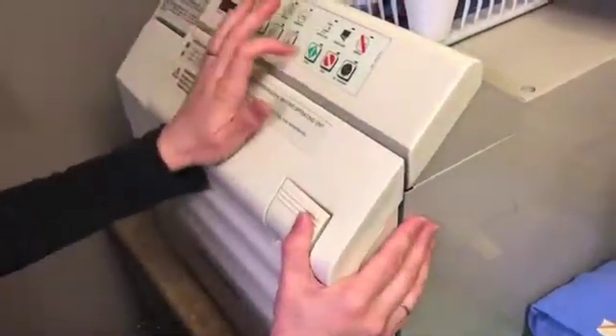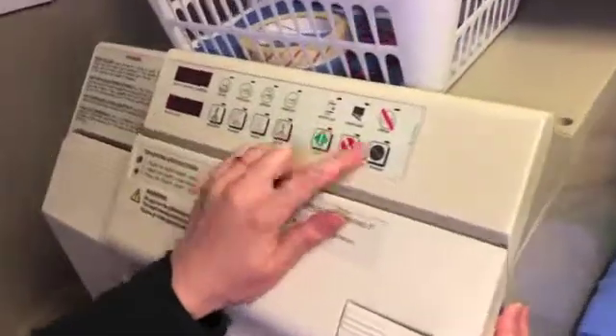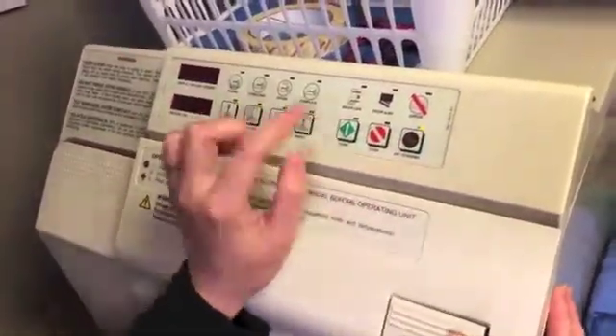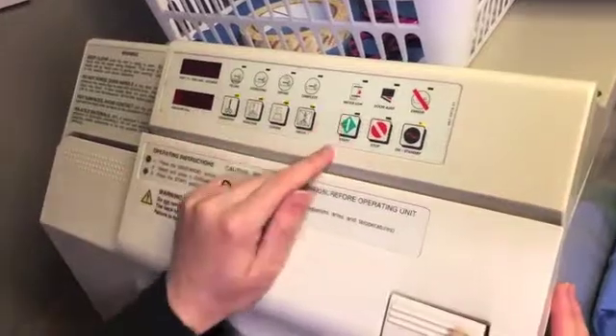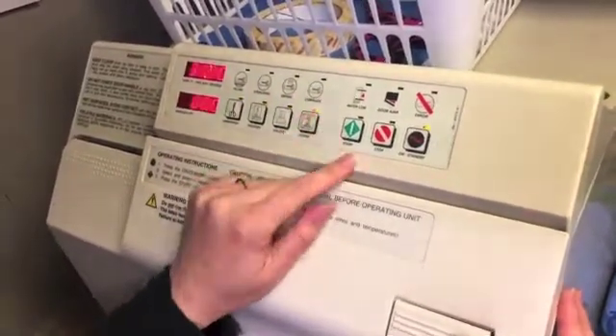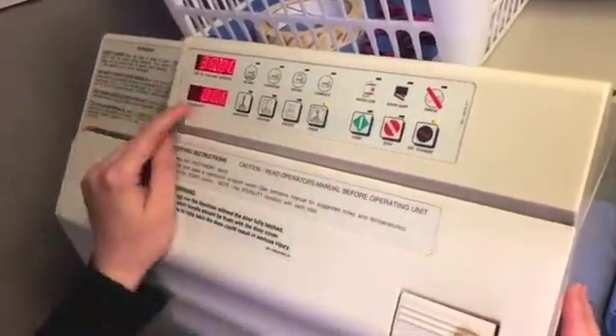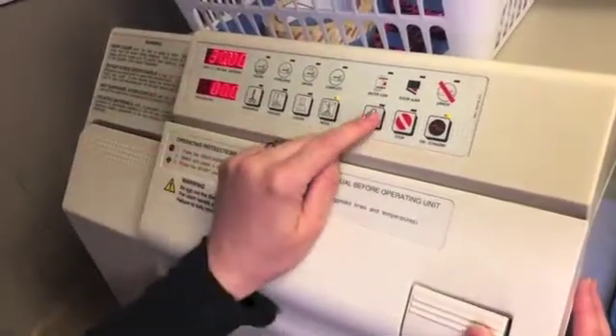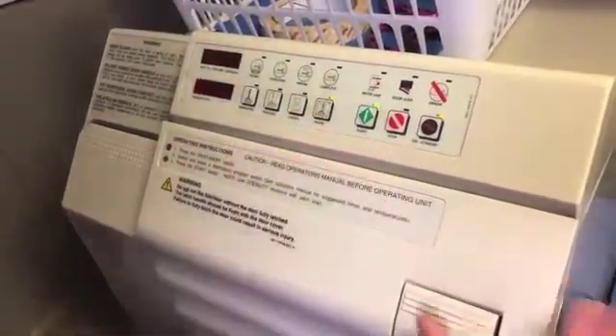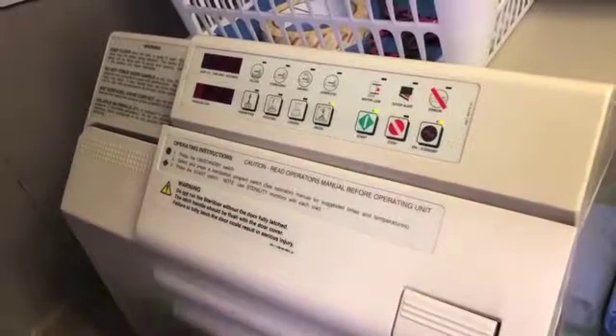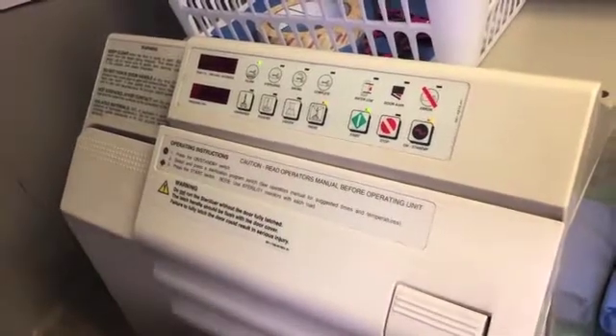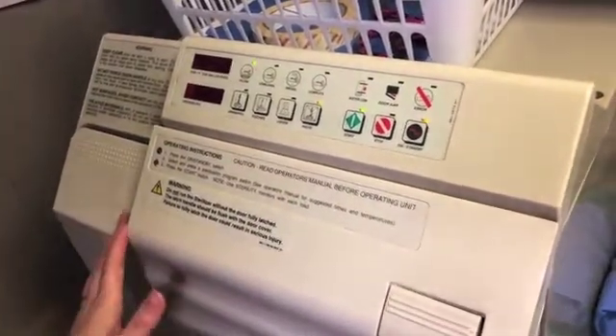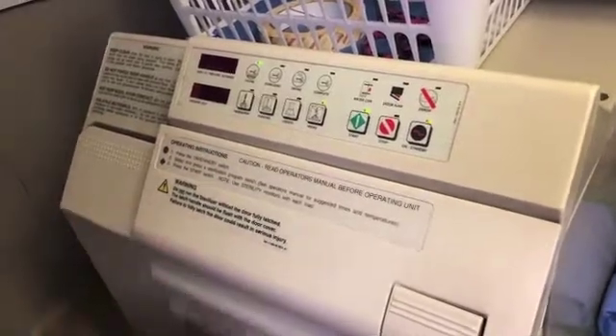We lock our machine beforehand. We're going to go ahead and hit start. We're going to hit on. And then we're going to select what we have in there. So we have packs. And this one automatically sets it for the time and the pressure. And we'll hit start. And if the water was low, the door was open, anything like that, it would alert us. And now the autoclave pretty much does its own thing and it opens on its own and lets the steam out when it's ready.